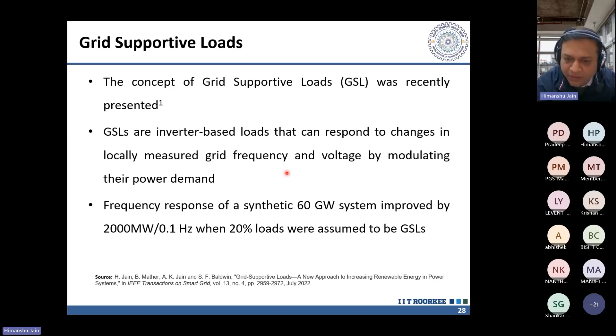of frequency-based modulation of power output. And what we observed there was that we could change our power demand by up to 2000 megawatt for every 0.1 hertz change in the frequency. And 20% of loads were assumed to be grid supportive loads.